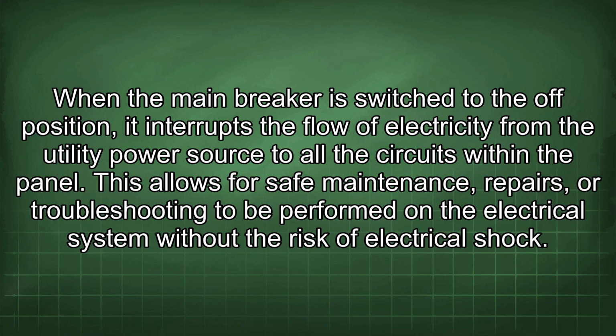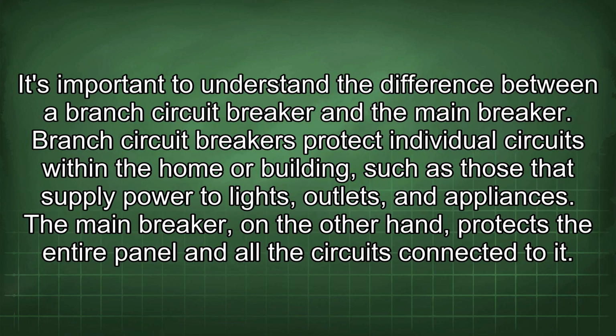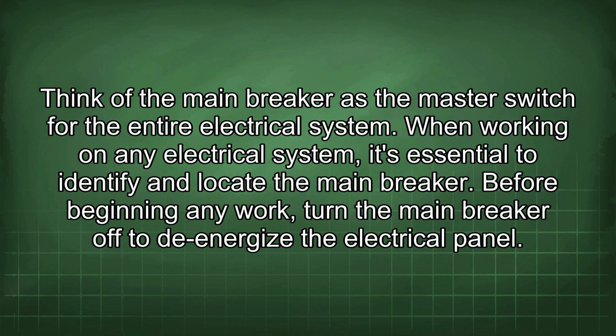This allows for safe maintenance, repairs, or troubleshooting to be performed on the electrical system without the risk of electrical shock. It's important to understand the difference between a branch circuit breaker and the main breaker. Branch circuit breakers protect individual circuits within the home or building, such as those that supply power to lights, outlets, and appliances. The main breaker, on the other hand, protects the entire panel and all the circuits connected to it. Think of the main breaker as the master switch for the entire electrical system.